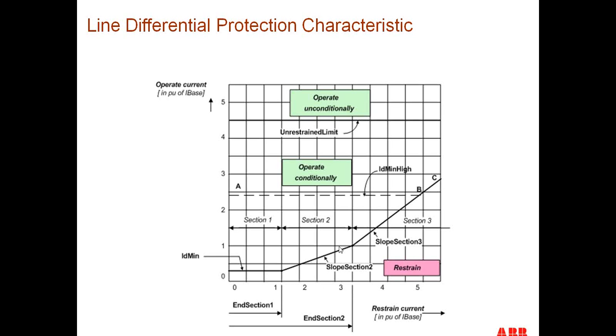And then we have the slope of section 2 and slope of section 3. I said before that this normal slope of section 2 would be set at 40%. The slope of section 3 would be set at 80%. In addition to this normal operating slope, this would be the conditional operating for the relay.